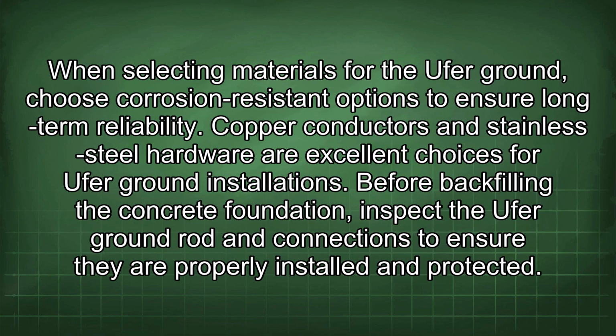When selecting materials for the Ufer ground, choose corrosion-resistant options to ensure long-term reliability. Copper conductors and stainless steel hardware are excellent choices for Ufer ground installations. Before backfilling the concrete foundation, inspect the Ufer ground rod and connections to ensure they are properly installed and protected.